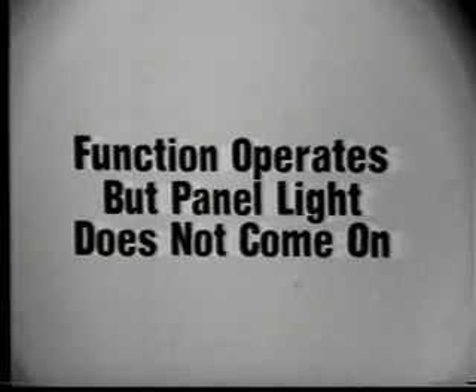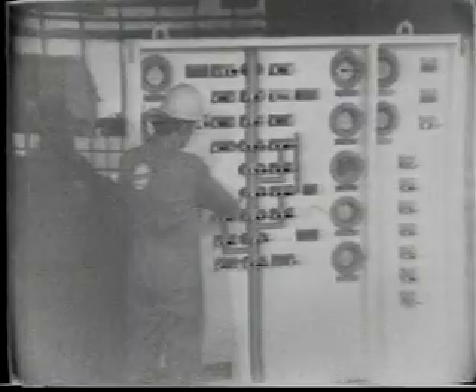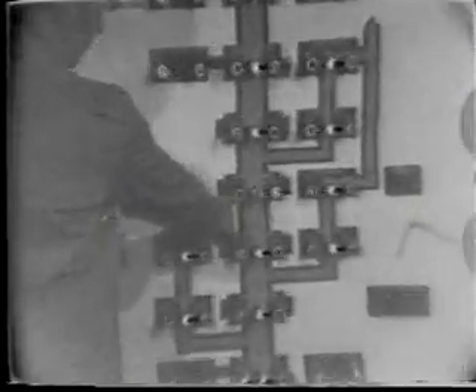Next, we will consider the items to check when the following malfunction occurs. A button is pressed, the function operates, but the light on the panel does not come on. First, you should press the lamp test button to see if the bulb will burn. If it does not come on, then replace the bulb and see if the function button will light up after the bulb has been replaced. If the new bulb will not burn, next check the lamp socket. If voltage is present, it may be necessary to replace the socket if it is defective.